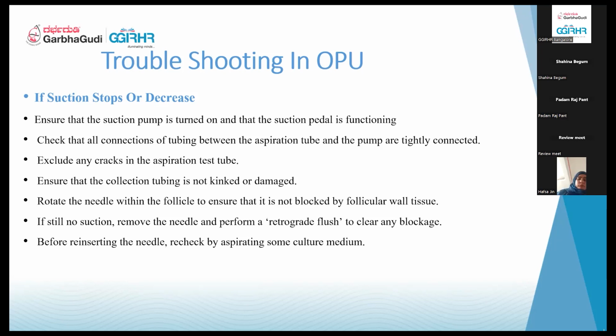You do it prior to the procedure also. Before starting the procedure itself, you will check whether the pedal is working, whether the suction pressure is working properly, whether optimum pressure is reached, and whether the flow rate is maintained. All these things will be checked prior to the procedure. Even in between the procedure, if something like that happens, see whether the suction pump is working properly. Check that all connections, the tubing between the aspiration tube and the pump, are tightly connected. This is how suction is produced: by the vacuum. If proper vacuum is not created, then you don't get proper suction.